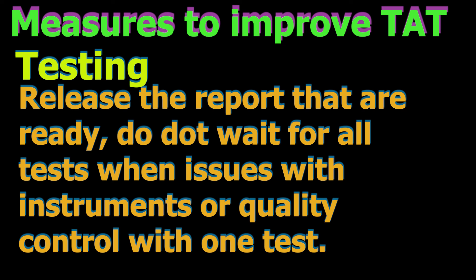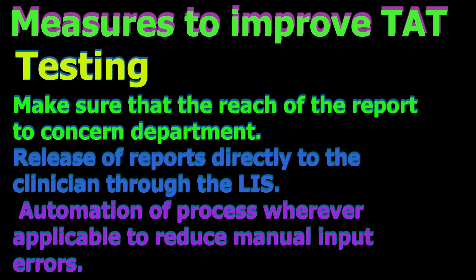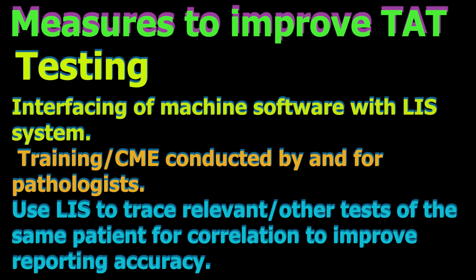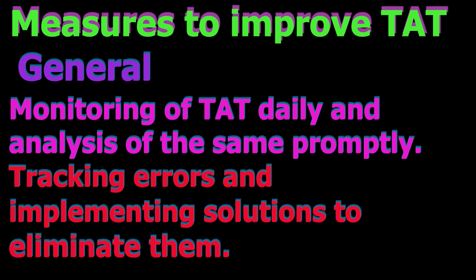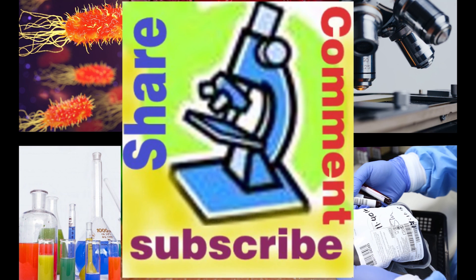If you have your own lab, timely reports build client confidence and increase referrals, raising the number of samples. It is always better to have two analytical instruments, both ready to run all stat tests — if one instrument is down or in service mode, the other can be used for stat samples. Make sure one instrument is always loaded with reagent and has good quality control results before taking the other instrument offline for calibrations, quality control, or maintenance procedures.